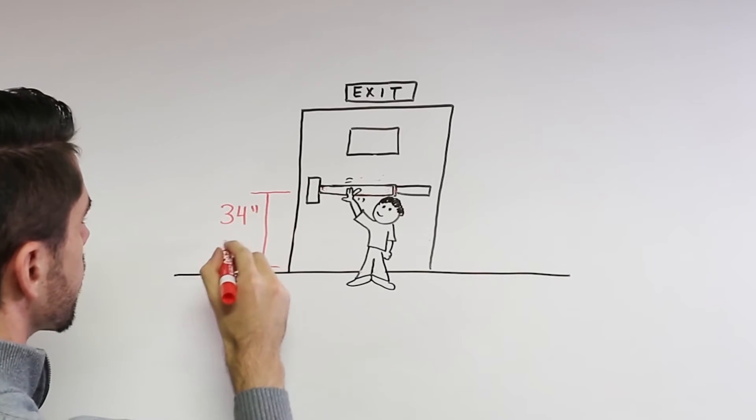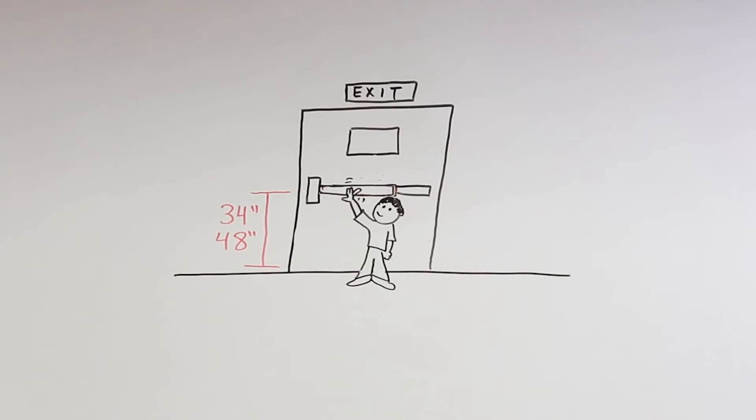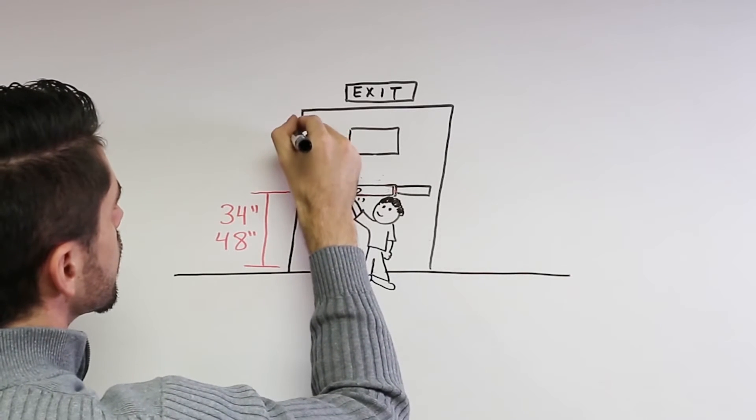Exit hardware must be mounted between 34 and 48 inches above the floor. Again, in an emergency, we don't want anyone to have to search for the device.